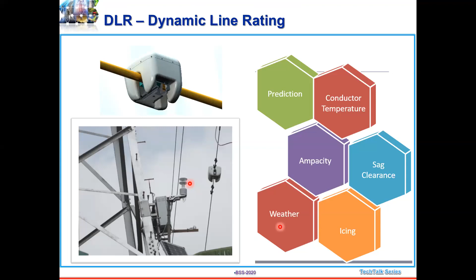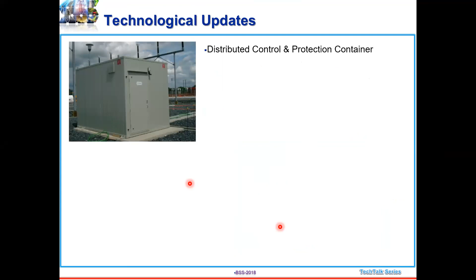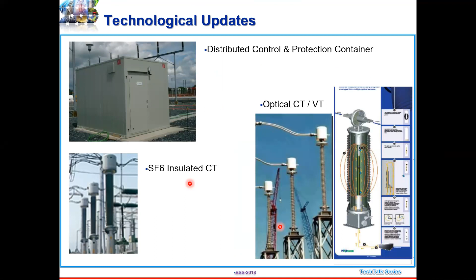This is a distributed control and protection arrangement, a technological update we are using. Nowadays relays and controls, which used to be in the control room in earlier days, are being placed inside the yard, so that fewer copper cables come into the picture. SF6 insulated switchgear is also being used, and that is also planned for this introduction. Optical CT/VT units are not yet available in KSEB, but in the near future that will also be available once the technology matures and the cost comes down.